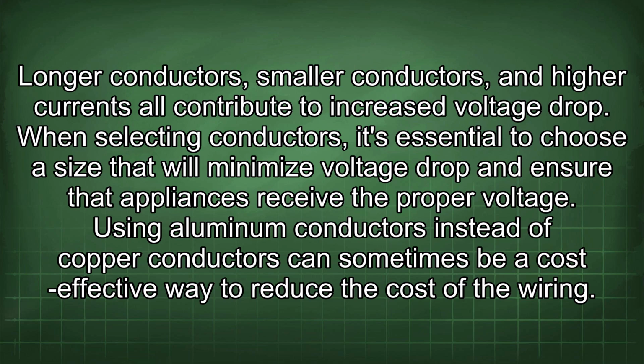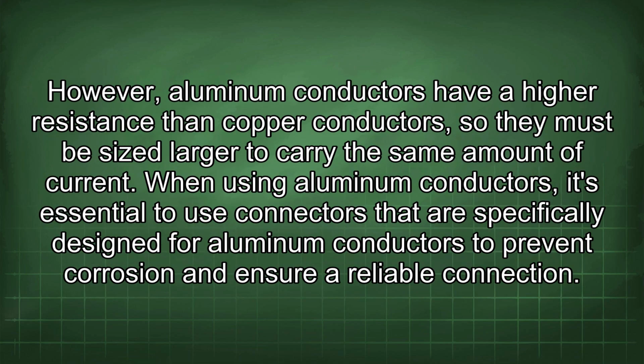Using aluminum conductors instead of copper conductors can sometimes be a cost-effective way to reduce the cost of the wiring. However, aluminum conductors have a higher resistance than copper conductors, so they must be sized larger to carry the same amount of current. When using aluminum conductors, it's essential to use connectors that are specifically designed for aluminum conductors to prevent corrosion and ensure a reliable connection.